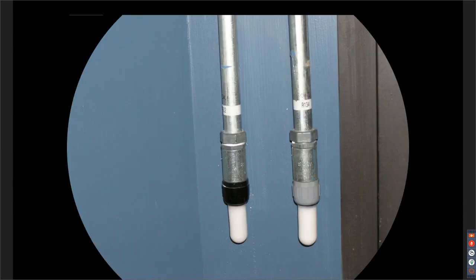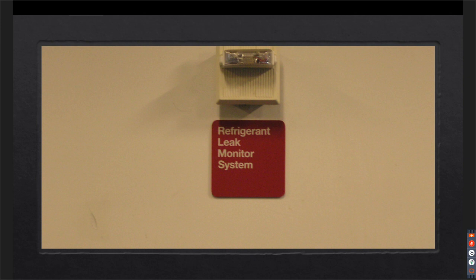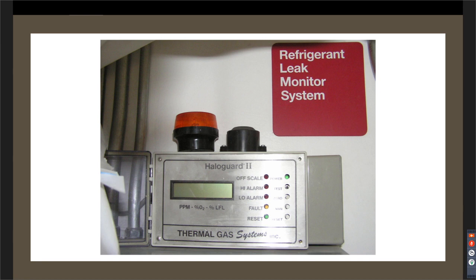They need to have the types of sensors for each of the refrigerants that might be in the room. The leak detection system has to have audible and visible alarms that are unique and dissimilar to the fire alarm system. So we don't want people to think that this is the fire alarm. They need to know this is a refrigerant leak.